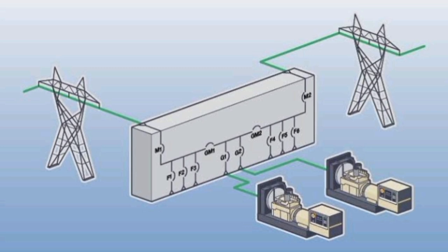In larger data centers, transfer logic is integrated into generator paralleling switchgear. This system detects voltage abnormalities, starts multiple generators, synchronizes frequency and phase, transfers load safely, and manages load sharing between units. This ensures a controlled transition from utility to generator power.